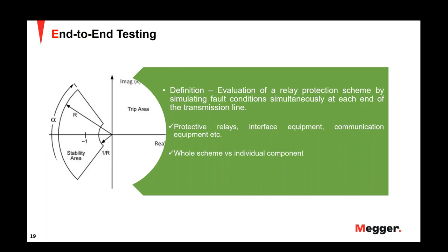So this type of testing allows you to test the entire scheme as a whole, in its natural environment. When you test the relays and the protection scheme with the communication, they would respond more closely as they would under real world conditions. And this can be used to perform testing on not just double-ended systems, but also multi-ended systems. You could have a three-terminal system and you can use end-to-end testing.